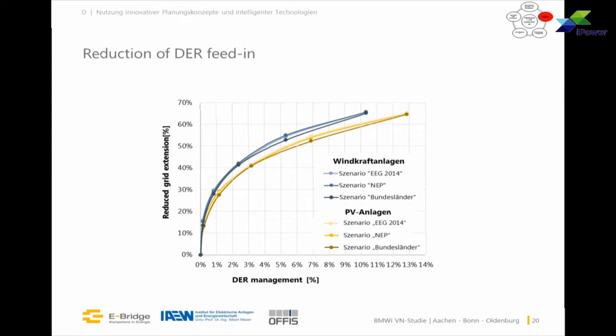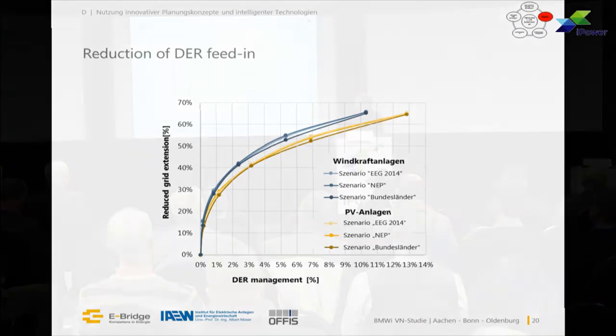One big issue is if you cut the DER peak feed-in. That's something envisioned by the local German utility in Oldenburg, the EWE. They said they use a 5% approach - cutting the upmost 5% of the DER load - and found out that saves a lot of grid extension. We calculated that for individual scenarios, taking into account both wind power plants and PV power plants.